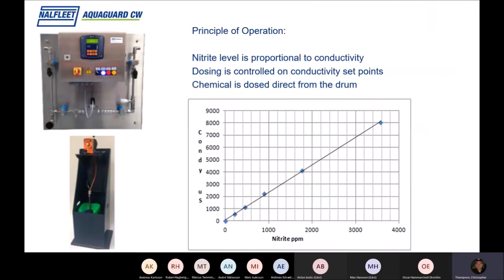Cooling water, on the other hand, this is what we call active testing. On the top right hand picture, you'll see the pipework. From the left, it comes in, goes down, then goes horizontal again. Halfway through, underneath the screen, you'll see a wire attached to a probe. That's a conductivity probe. So the water will pass the probe, we'll see what the conductivity is, and a good cooling water conductivity is 2.5 to 3,000 microsiemens, which will give you 1,500 ppm of nitrite.